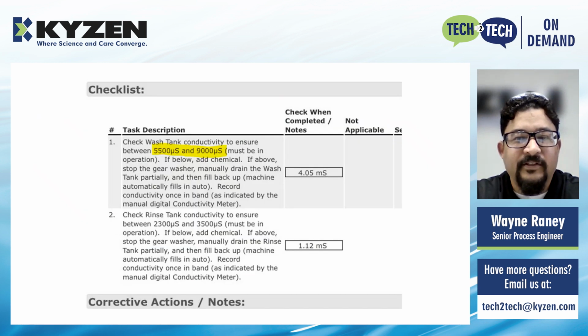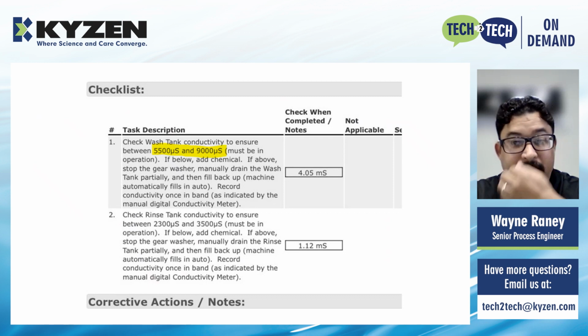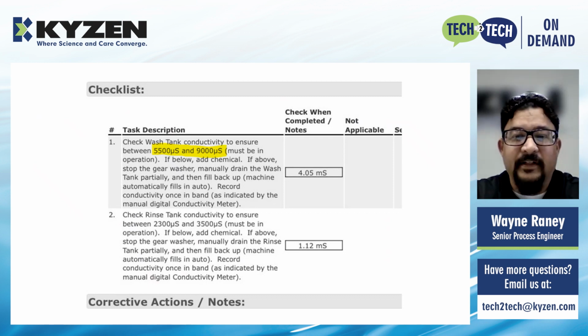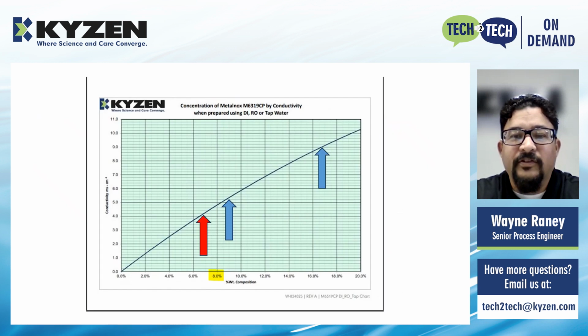We also noticed that the customer specification is recorded at 5.5 millisiemens to 9.0 millisiemens. They stated that their spec is 8%. So our calibration check reading was noted to be low, and also their spec needed to be changed. So we cleaned the probe and they went in their preventive maintenance system and changed their specification. Again, the two blue arrows indicate what they had as their upper control limit and lower control limit. Notice that this does not contain their specification of 8%, which again is highlighted in yellow.